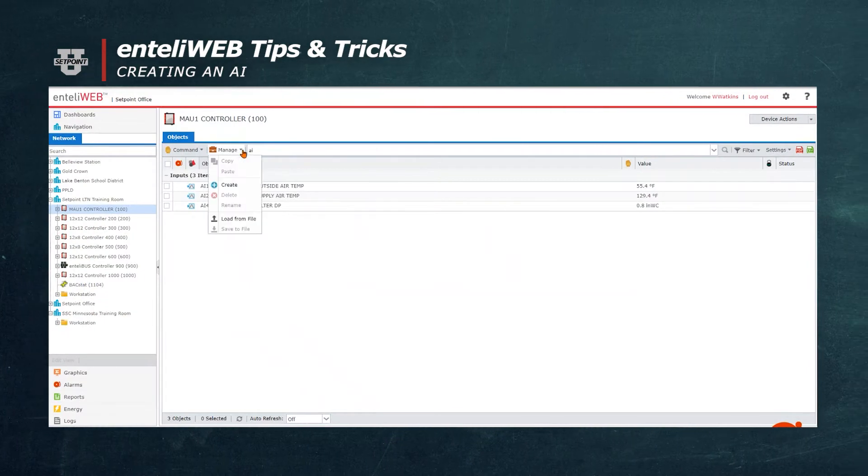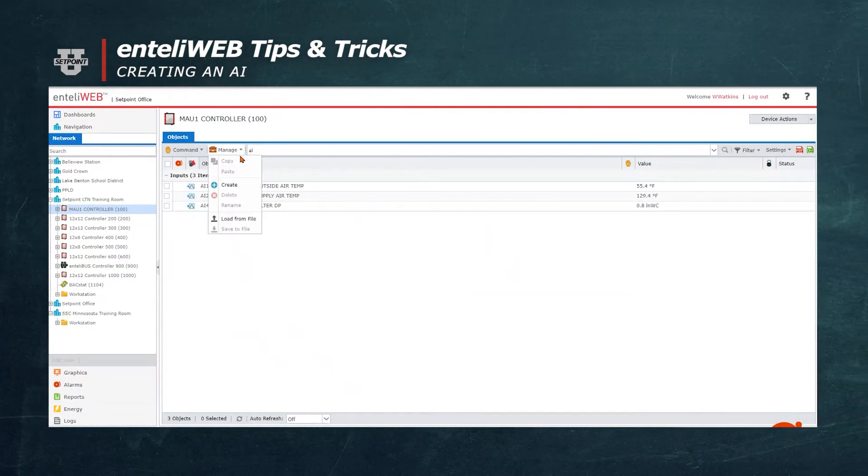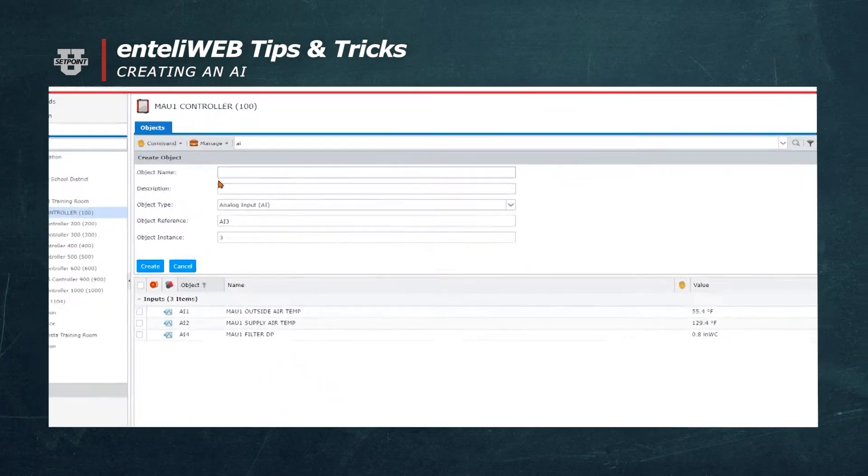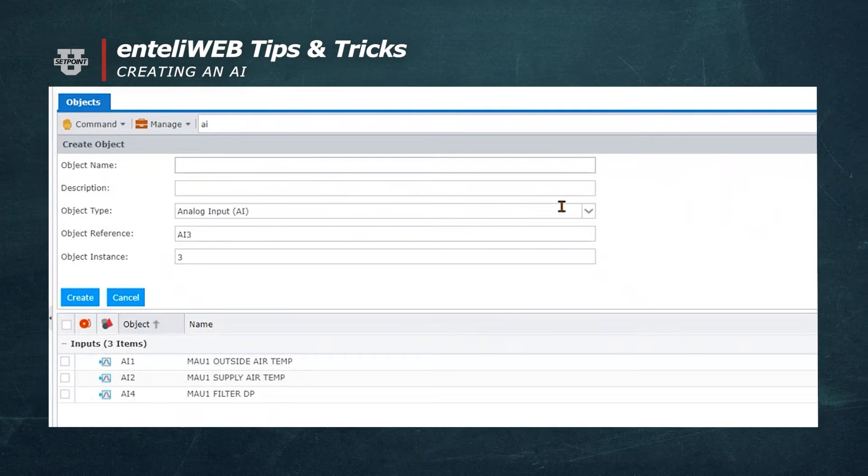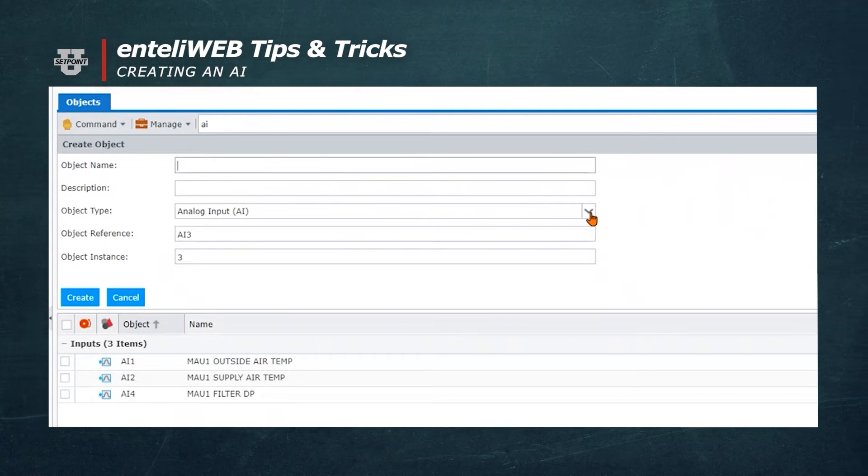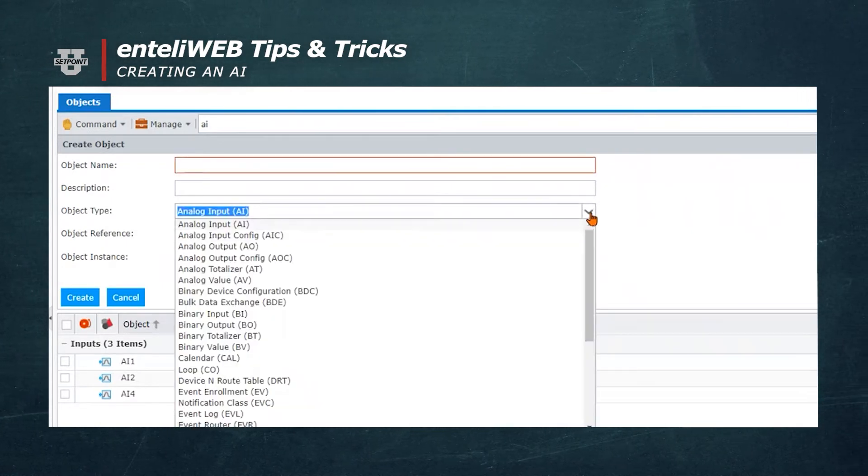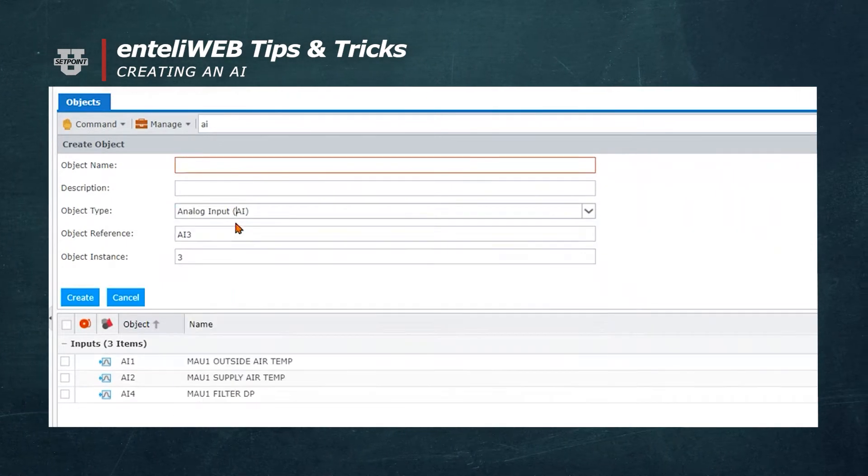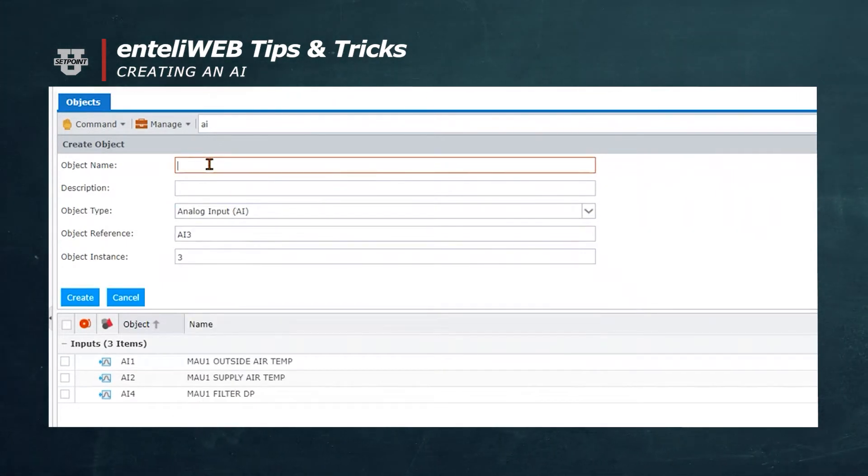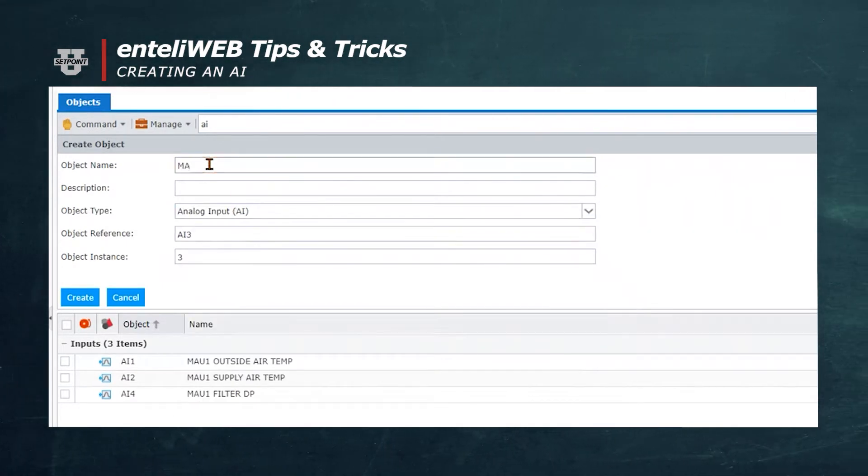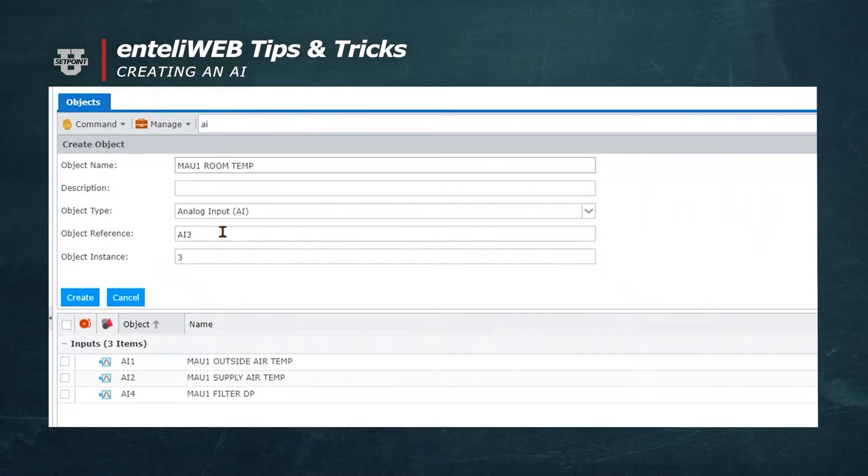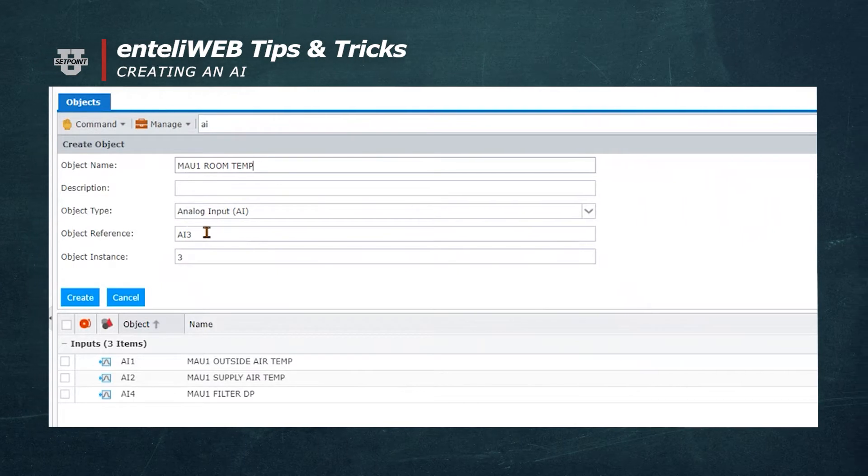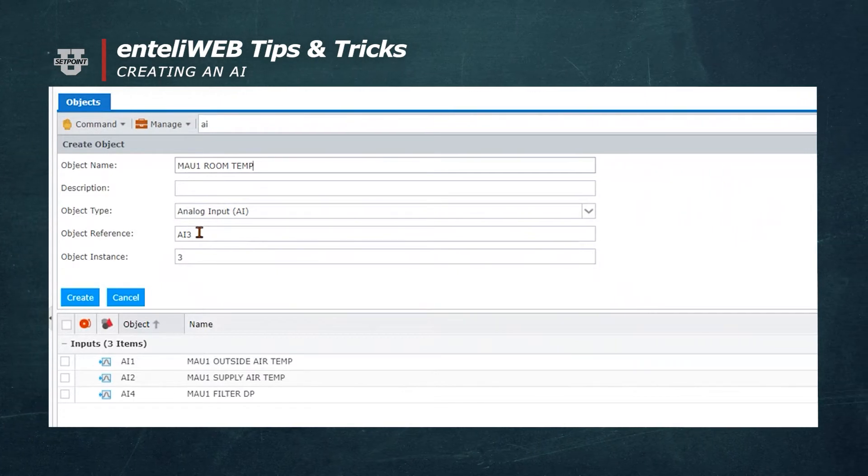To create an analog input, I will now go to the Manage button and select Create. I'm going to select an object type, that's an AI. You'll notice it was already there, so now we're going to give it a name of MAU1 room temperature. The object reference is AI3, which is the next available analog input.